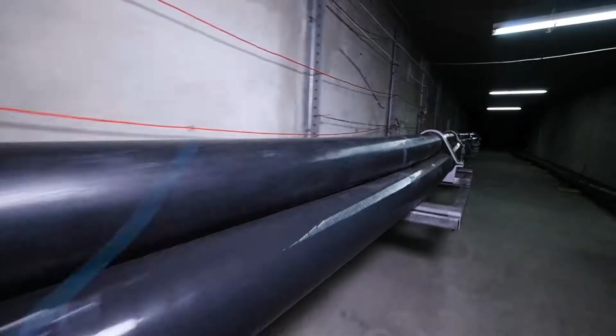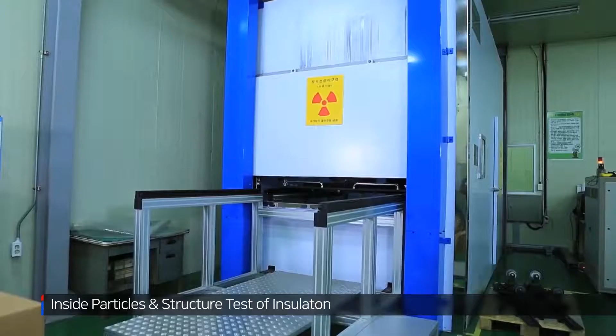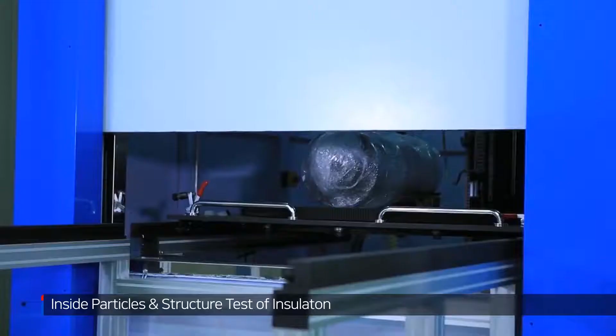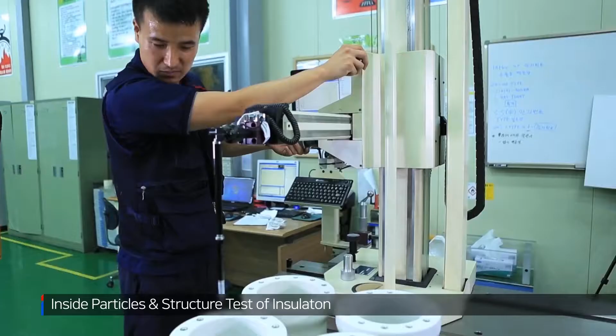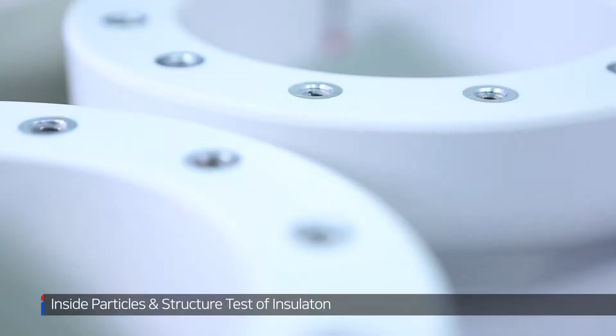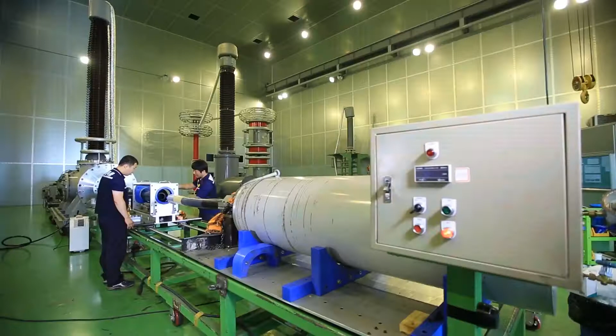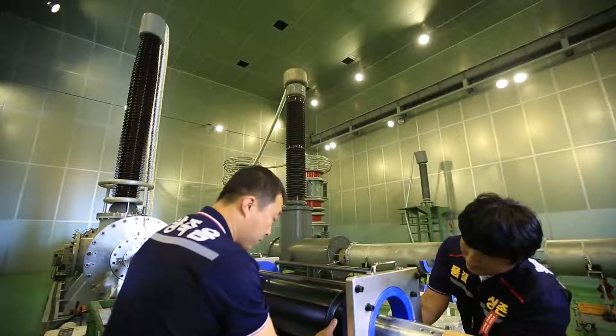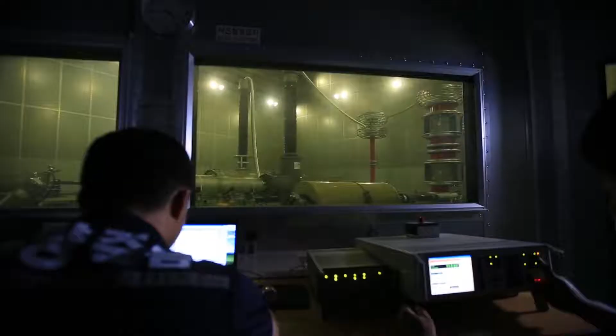EHV accessory plant has its own test laboratory and PQ test field. Hence, all relevant PQ test and type test can be physically performed in-house. In the test laboratory, they can test if there is air and/or particles inside the insulation with an X-ray and an ultrasonographic measuring instrument, and perform structure and measurement test with layout machine. In the shield room, we carry out the routine and third-party witnessed inspection test by AC 600 kilovolt high-voltage tester and PD test equipment.